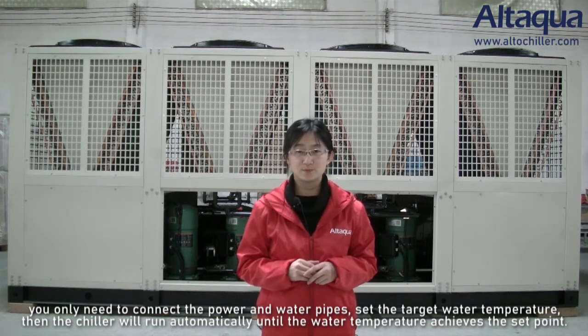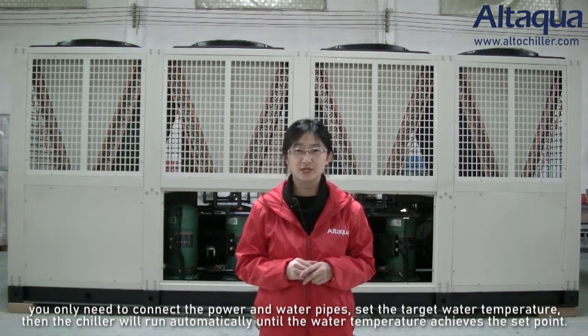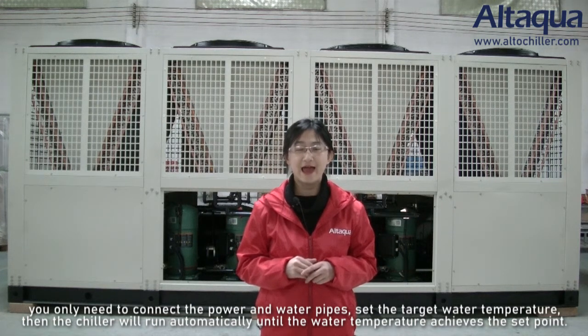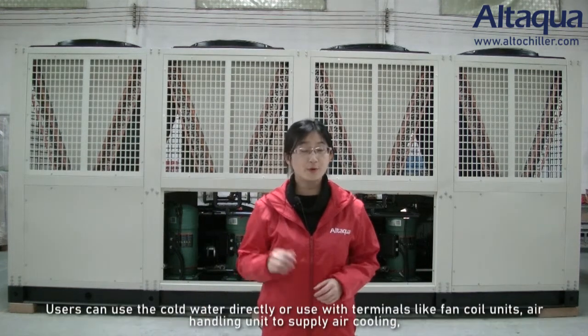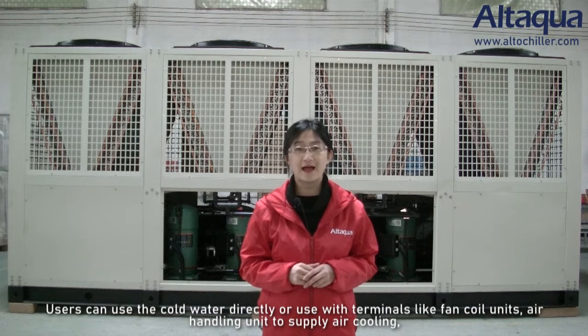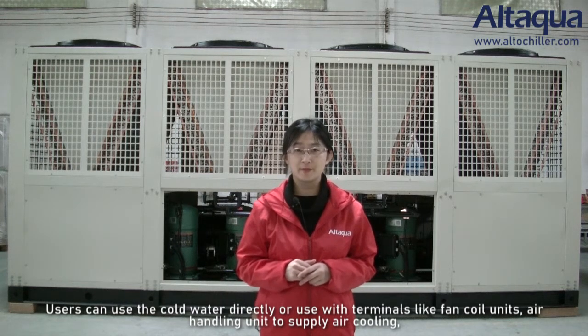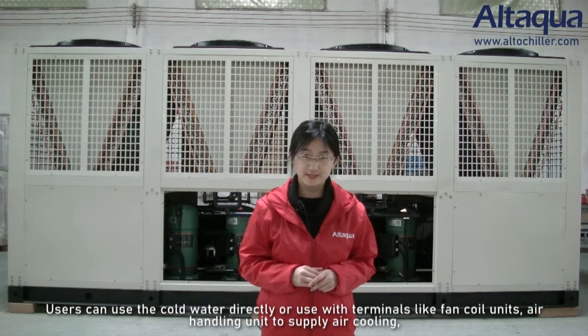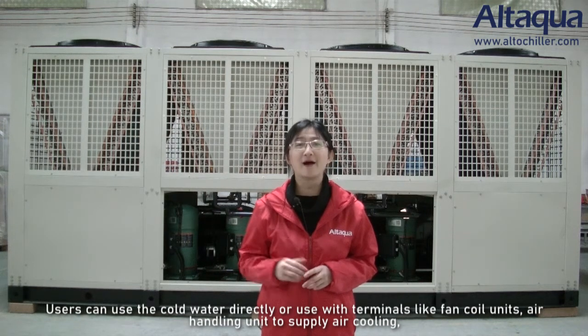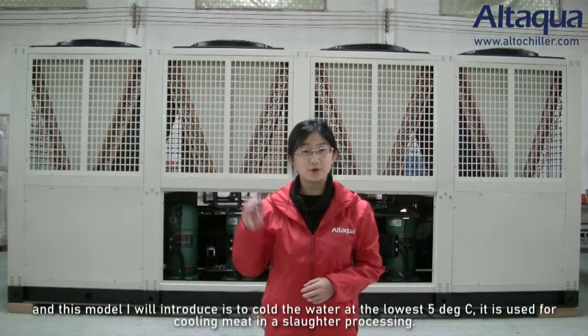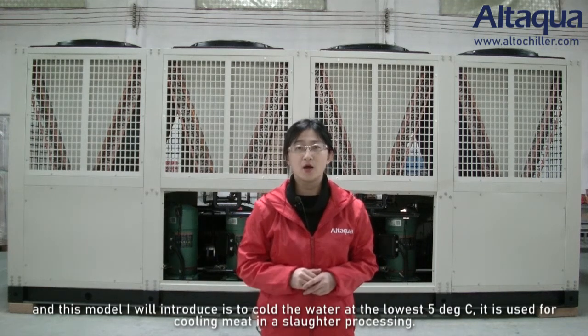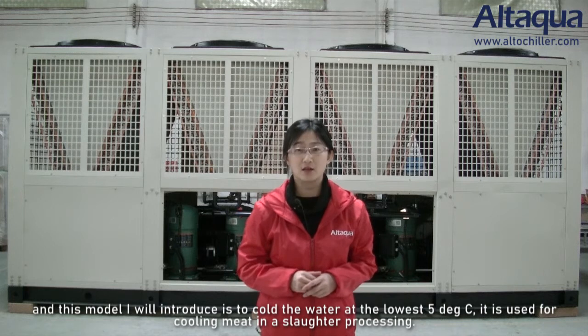Then set the target water temperature, and the chiller will run automatically until the water temperature achieves the set point. So users can use the cold water directly or use it with terminals like fan coil units and air handling units to supply air cooling. The model I will introduce cools the water to 5 degrees centigrade at the lowest. It is used for cooling meat in slaughter processing.